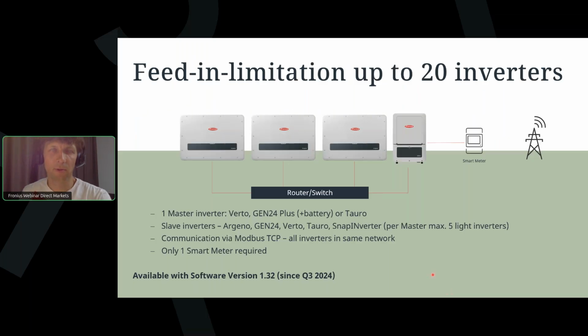If you want to do power limitation to the grid, you should use another Fronius inverter, because Argeno can only work as a slave inverter, and the master should be Verto, Gen24, or Tauro inverter. You can use up to 20 inverters in one system with one smart meter.